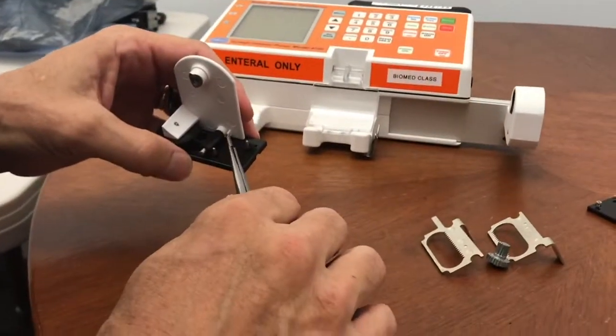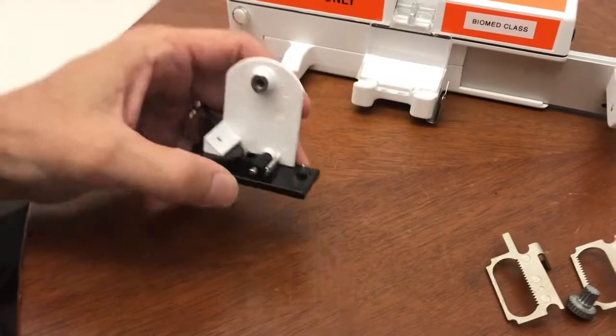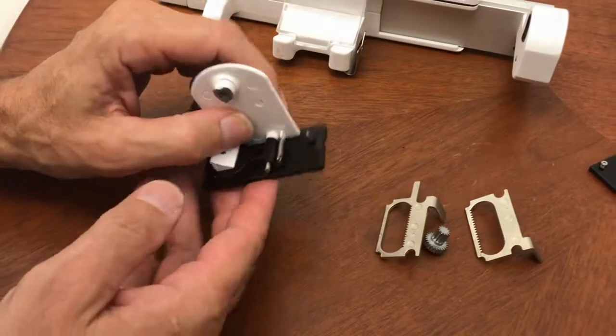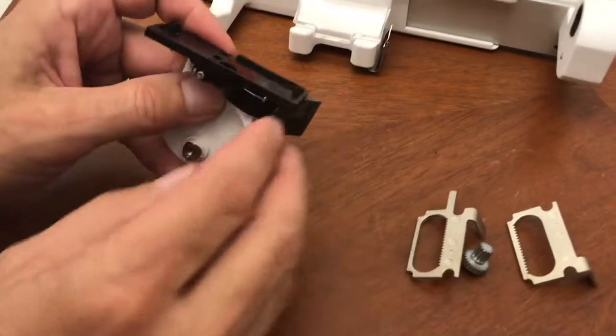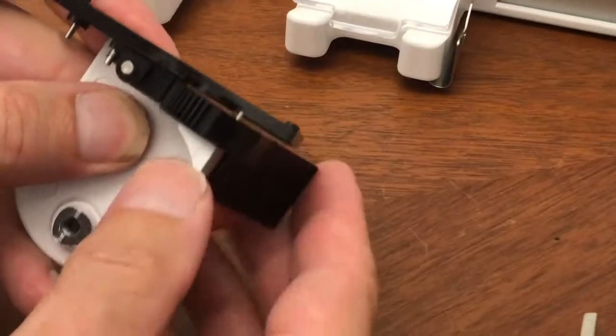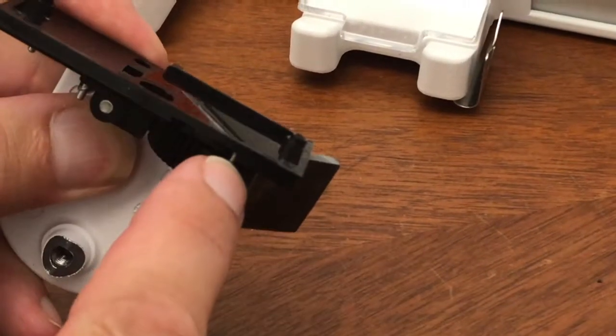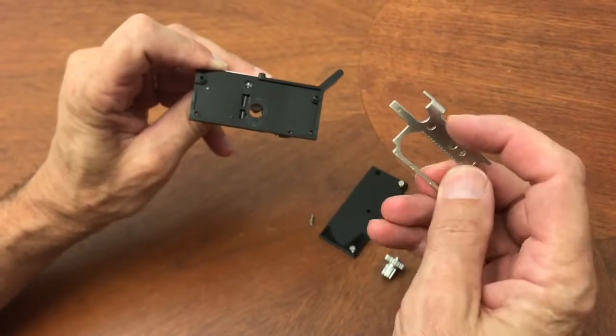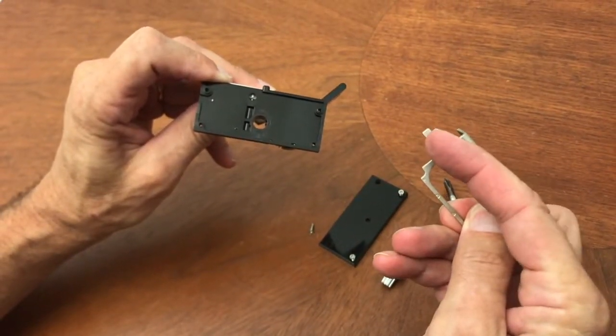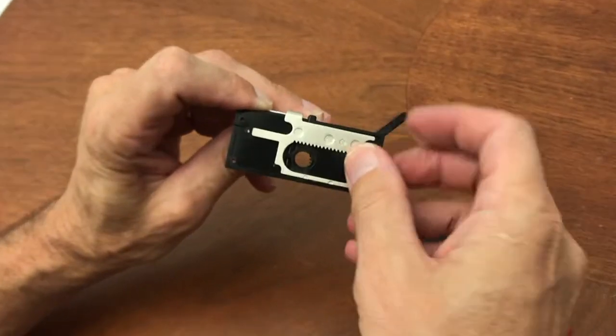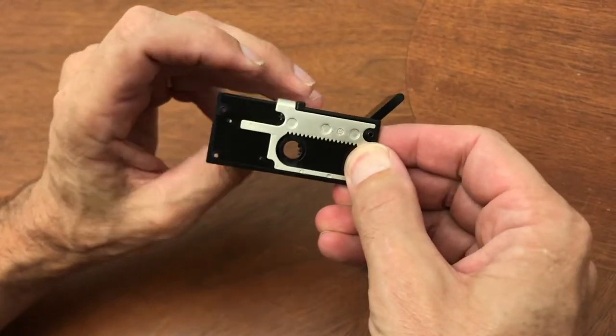And then place the spring back over the pin. Then take that assembly, turn it over. Note the pin in the bottom of the lever needs to fit into that notch of the retainer top. The next step would be to put this bar in, the bar that has the little arm right here. Put that bar in that orientation.